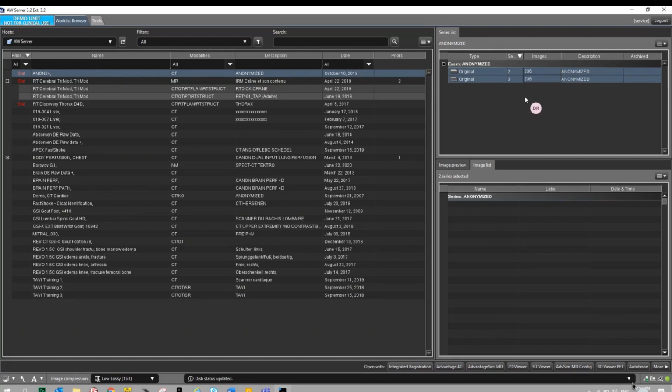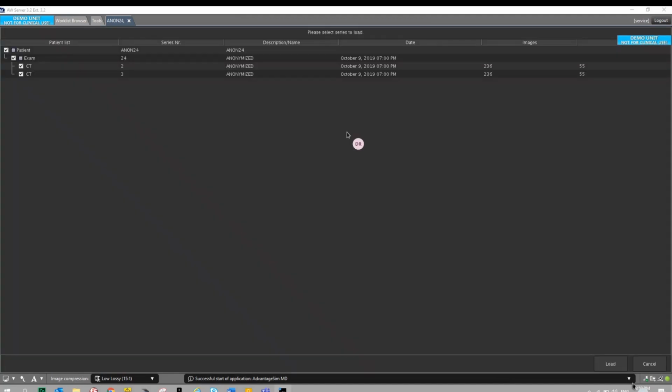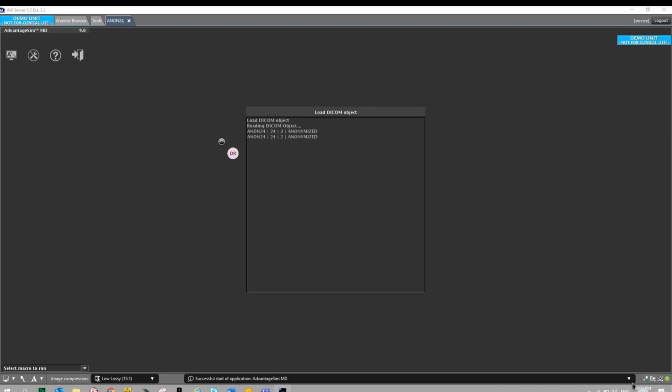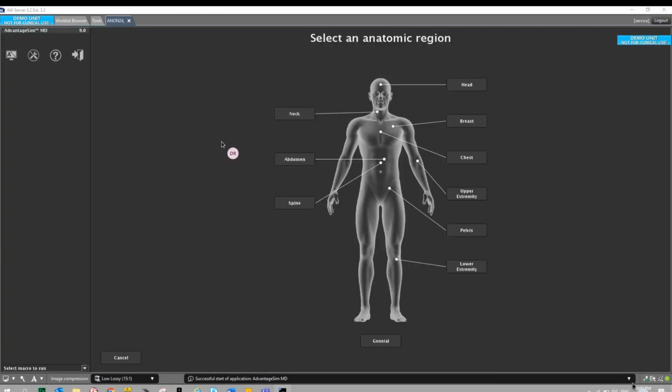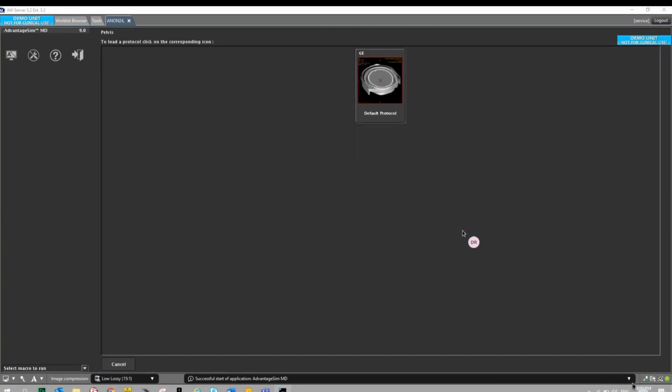We can acquire the different data at 2 energy levels, and whatever the energy level used, the system will compute automatically, by analyzing the defect from the beam hardening provided by the metal artifact, and ensure the correction to give both anatomical information and density information that can be used for the therapy.